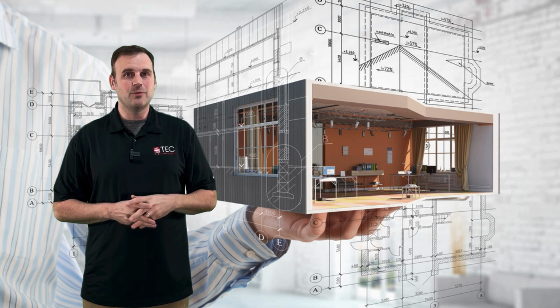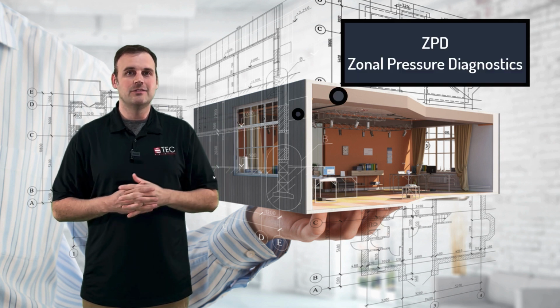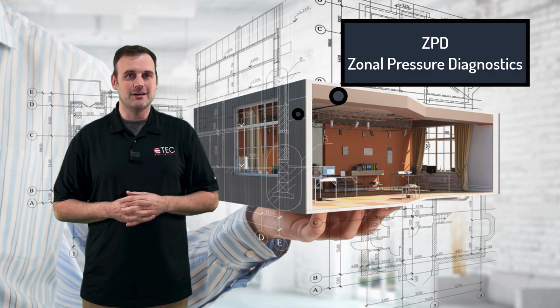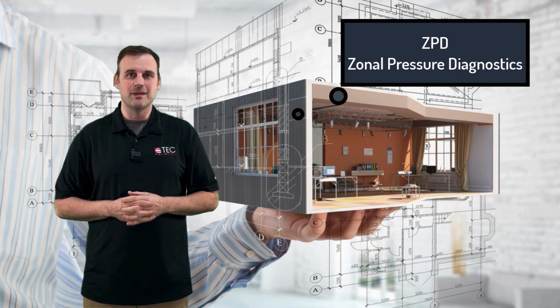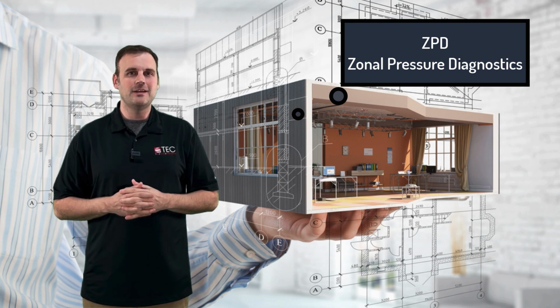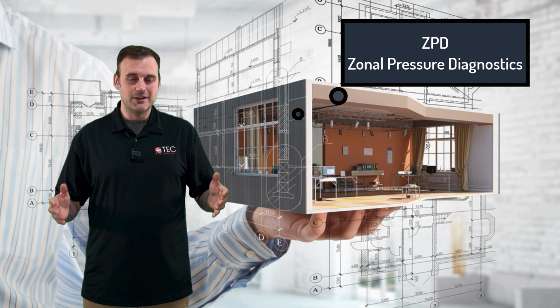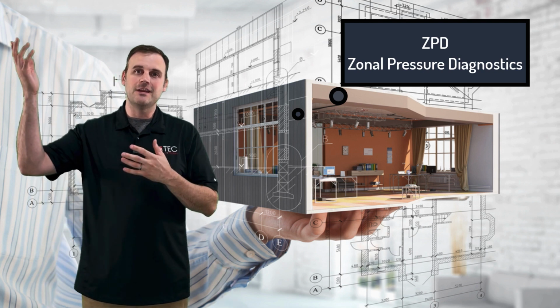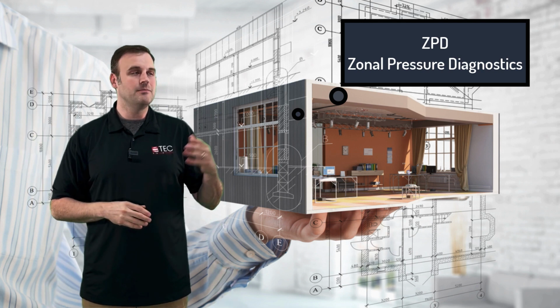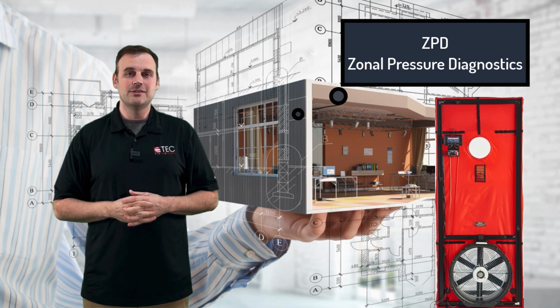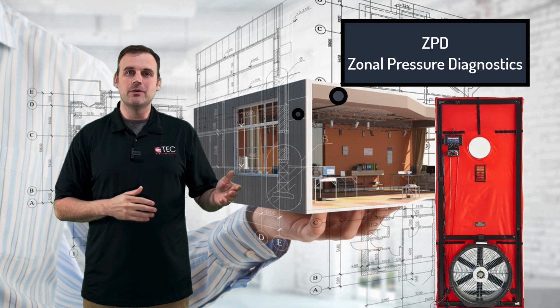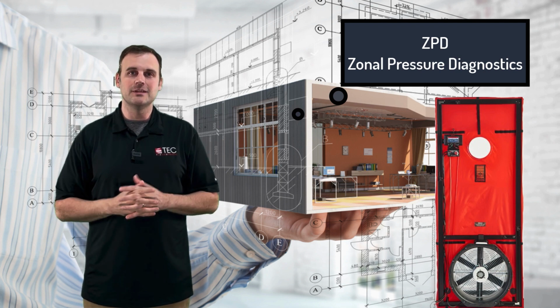We need to understand what ZPD means. Zonal Pressure Diagnostics. What does that mean? Easiest way for me to explain it is if I have a home and the home's on a slab and it has a vented attic. I would install a blower door in an exterior door. I would run the blower door on the home, establish the leakage.